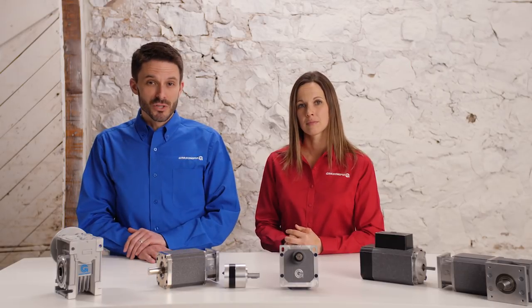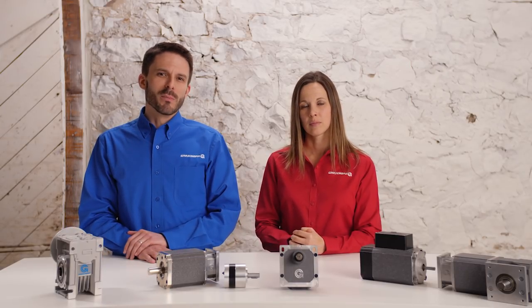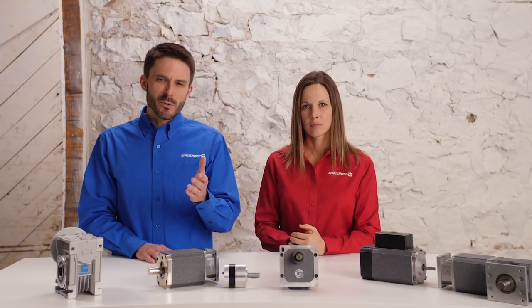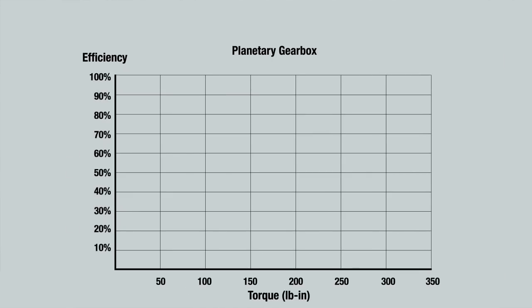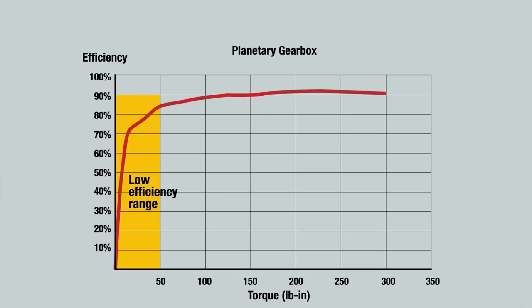Next we need to look at the efficiency curve. It's important to review these curves when making a reducer selection, so be sure to get them from the manufacturer. Our sample curve is for a planetary gearbox and is a graph of torque versus efficiency. It's important to emphasize that efficiency is not constant with torque. This data is used to calculate the torque capacity of a gearbox from a thermal standpoint. An important observation is that selecting a gearbox that is too large for the application will result in operating in the low efficiency range of the curve. For instance, using this gearbox in an application with less than 50 inch-pounds of torque is extremely inefficient and is not using the gearbox to its full potential.